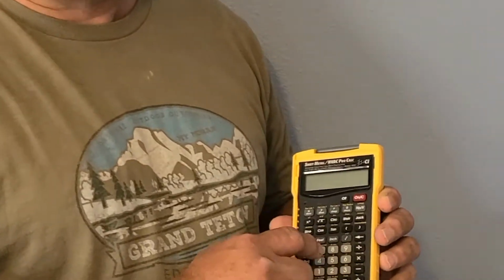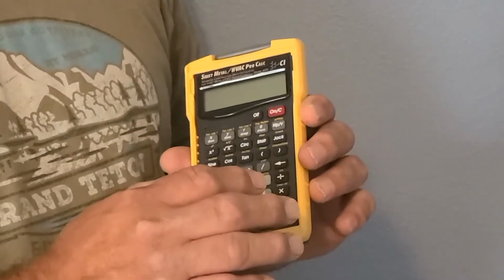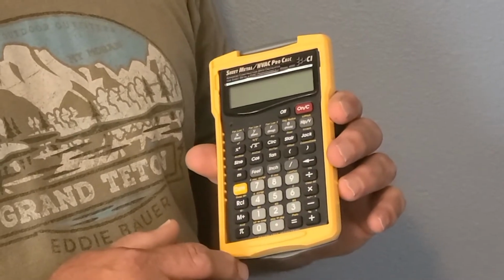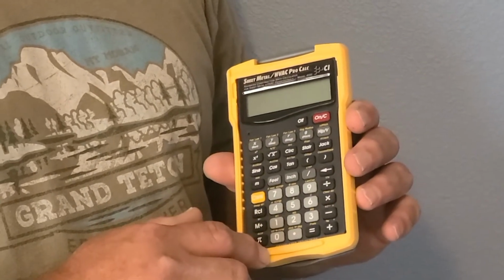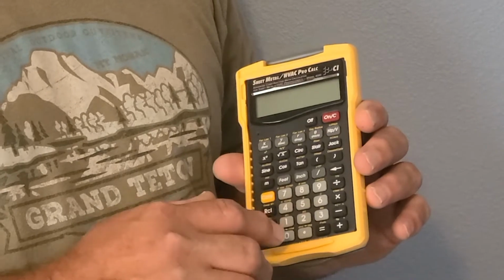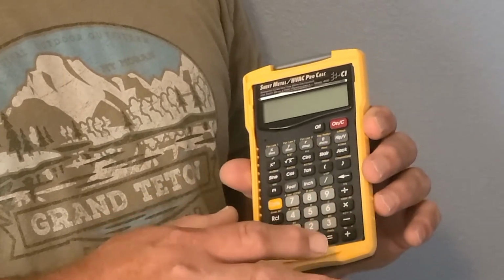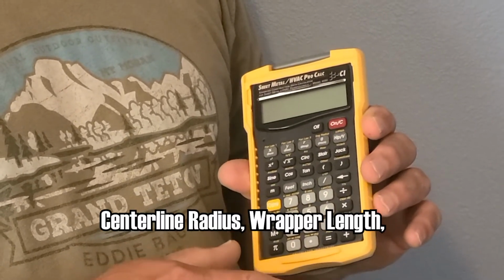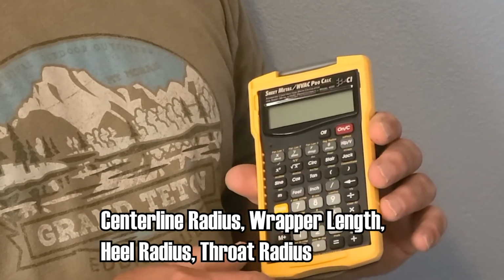To figure out the lengths and angles of an offset, let's look at an example. Our offset is 5 feet, the length is 10 feet, and the height of end A is 7 feet. We need to calculate the centerline radius, wrapper length, heel radius, throat radius, and theta.